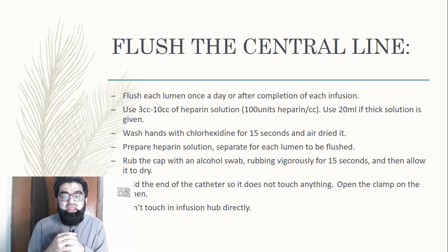Open the clamp on the lumen and don't touch the infusion hub directly. Remove the cap from the cannula and needle and insert into the injection cap. Slowly inject the entire amount of heparin into the lumen of the catheter. If you meet resistance, check to see if the clamp is closed. If there is still resistance, do not flush the lumen. Call the doctor. Call some senior doctor.